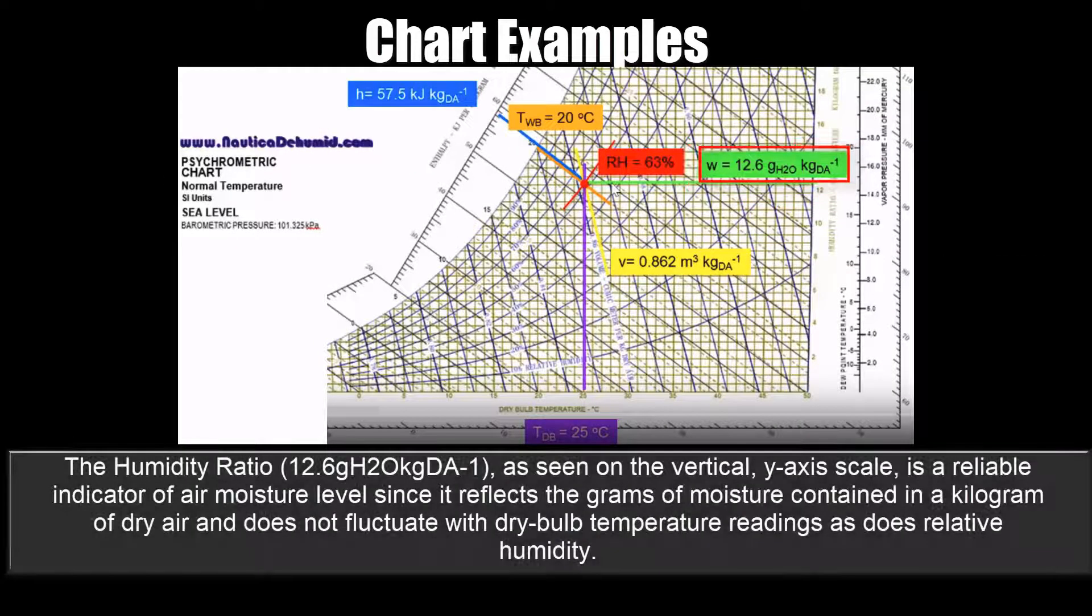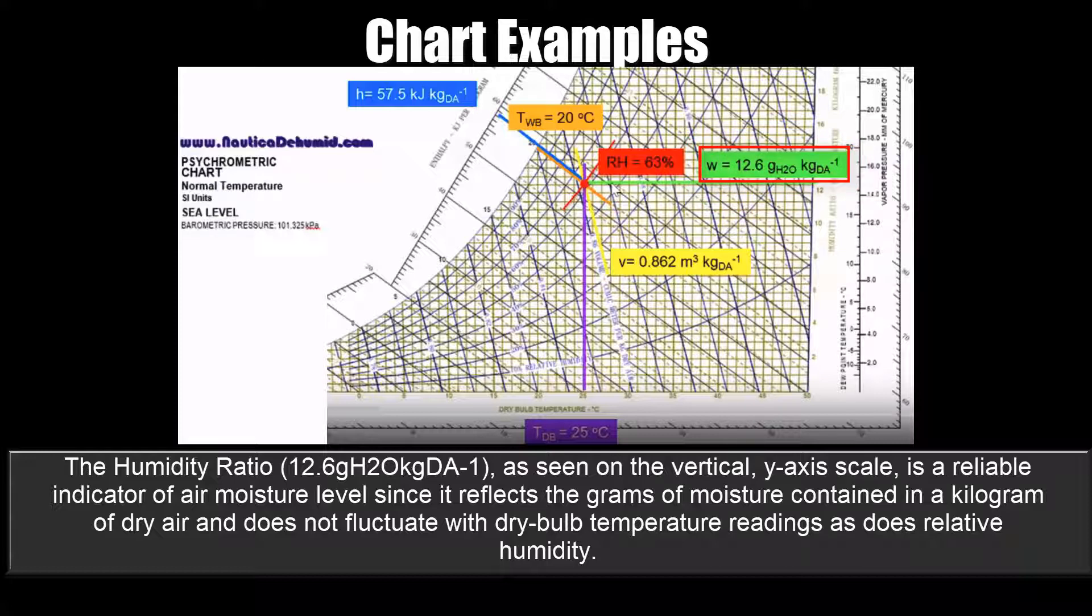The humidity ratio, as seen on the vertical y-axis scale, is a reliable indicator of air moisture level since it reflects the grams of moisture contained in the kilogram of dry air and does not fluctuate with dry bulb temperature readings as does relative humidity.